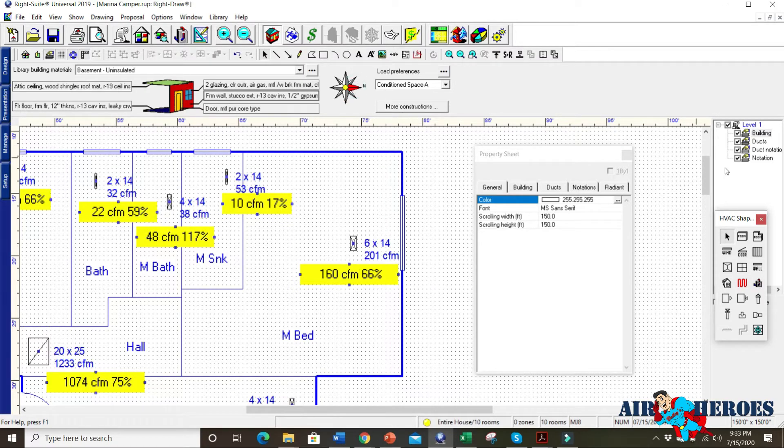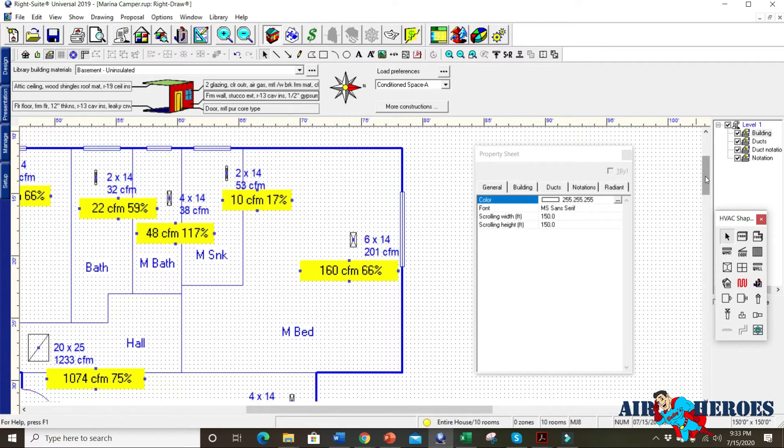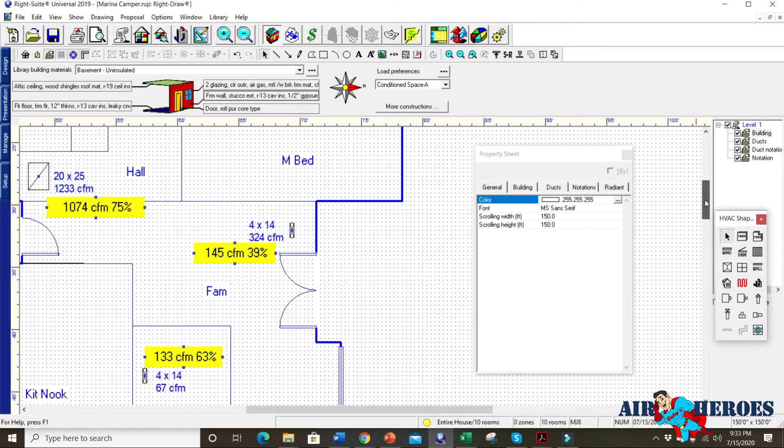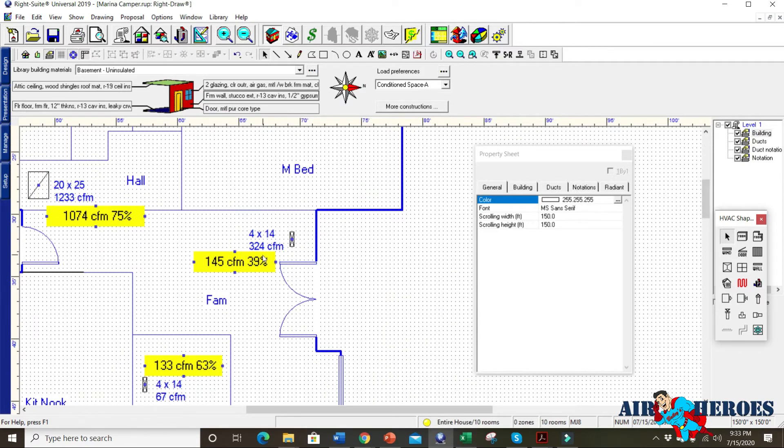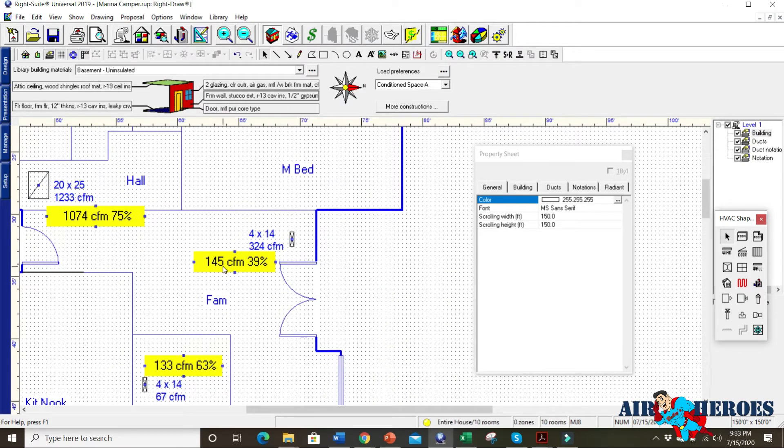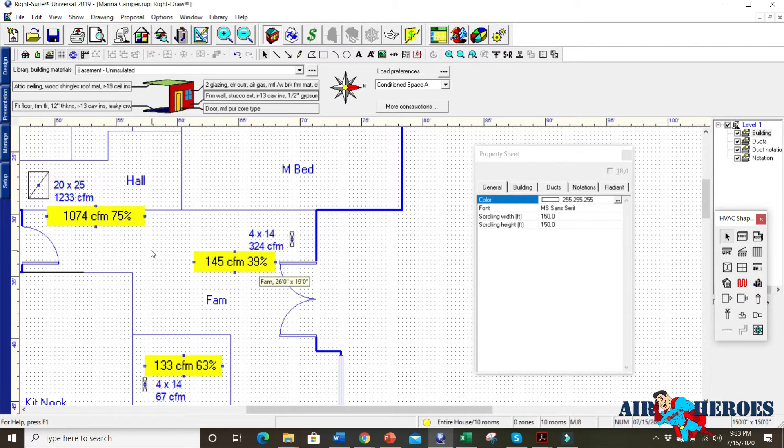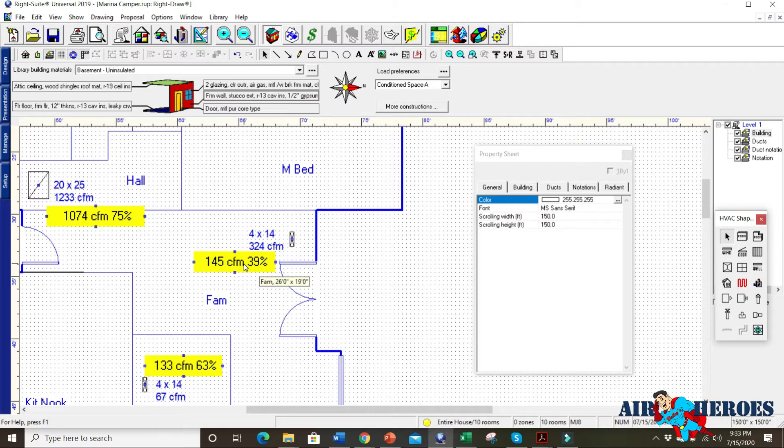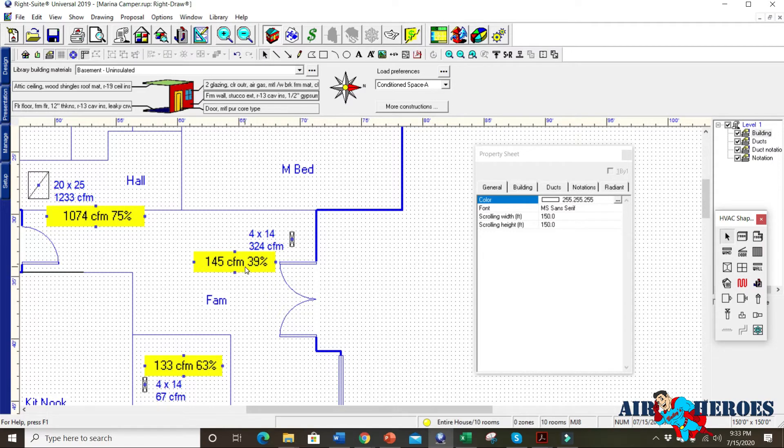And it's not so bad on this one, but let's take it back to north again. Let's take a look at down here at this living room register, the family room register is 145 CFM. It's supposed to be 324 and we're only getting 39% of the capacity it's supposed to. Now this is a three ton unit, which CFM stands for cubic feet per minute. There's another video later on that we should be posting online here, hopefully next week that explains all these acronyms that we use CFM, BTUs, AFUE, SEER, EER.